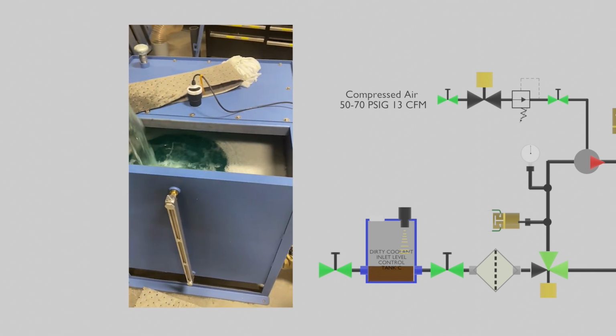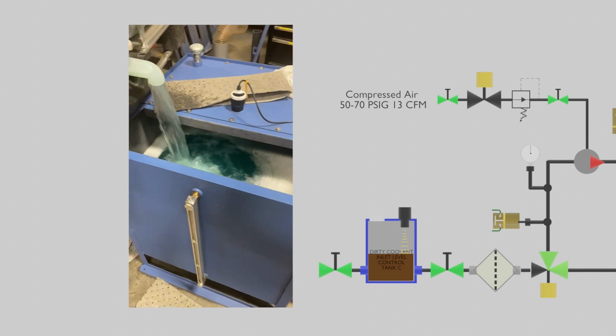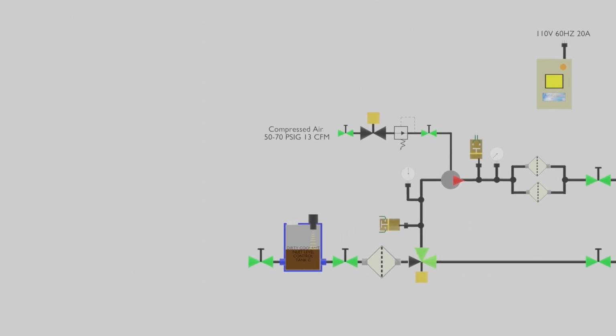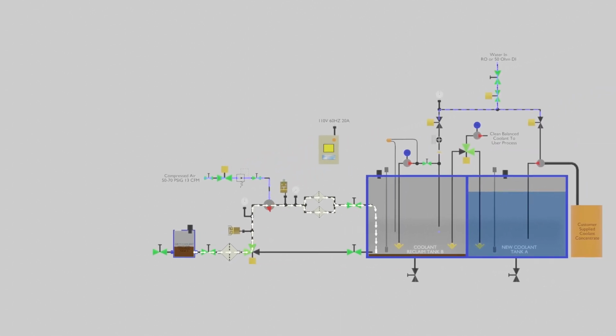When the Tank C ultrasonic level detector indicates that coolant in Tank C is high enough, and the ultrasonic level detector in Tank B shows coolant levels are low enough, the electric three-way valve shown here will switch to Tank B pump-in mode, and then a 24-volt air solenoid shown here will open, sending compressed air to the air diaphragm pump. The air diaphragm pump will then pull coolant out of Tank C through a 25-micron bag filter for pre-filtration, and then pump it into 2 large cartridge filters for polishing before entering Tank B.